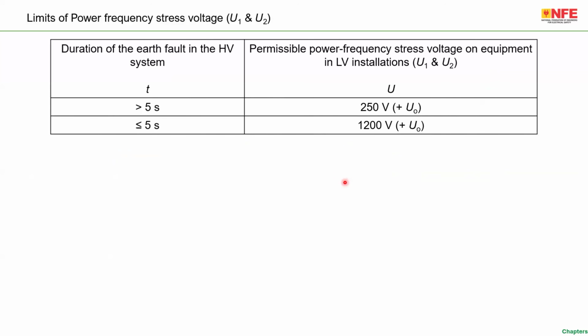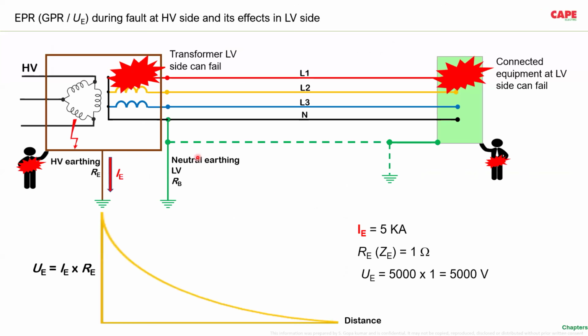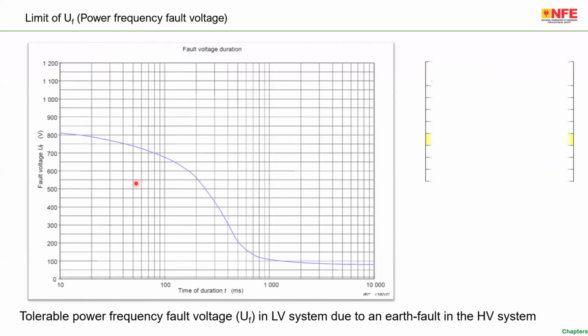The second one, stress voltage. What exactly is this stress voltage? Stress voltages arise when there is a fault on the high voltage side of the transformer. Stress voltage means, here I am moving the cursor, a voltage between the body of the transformer and the winding, or a voltage between the body of the connected equipment and a live conductor.